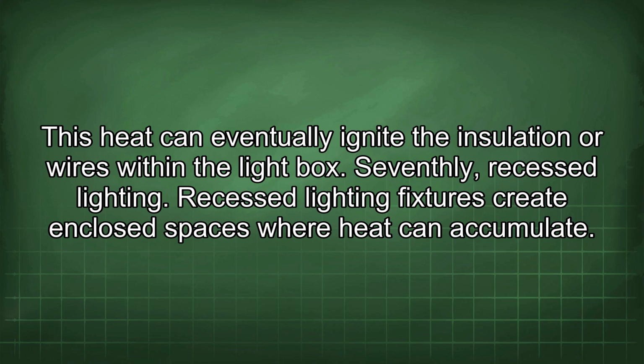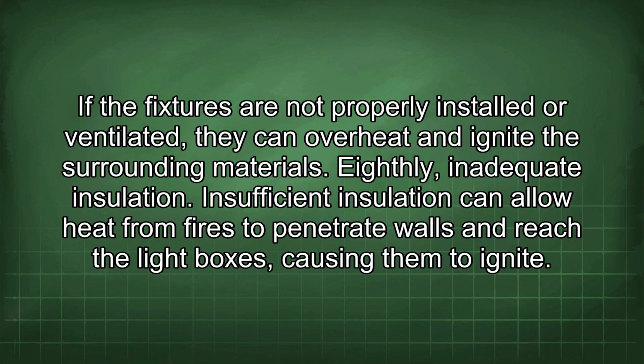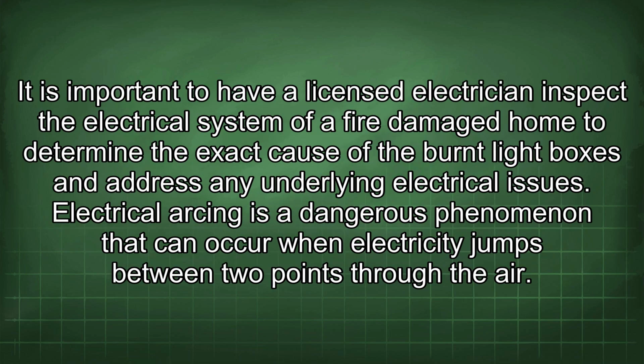Seventhly, recessed lighting. Recessed lighting fixtures create enclosed spaces where heat can accumulate. If the fixtures are not properly installed or ventilated, they can overheat and ignite the surrounding materials. Eighthly, inadequate insulation. Insufficient insulation can allow heat from fires to penetrate walls and reach the light boxes, causing them to ignite. It is important to have a licensed electrician inspect the electrical system of a fire-damaged home to determine the exact cause of the burnt light boxes and address any underlying electrical issues.